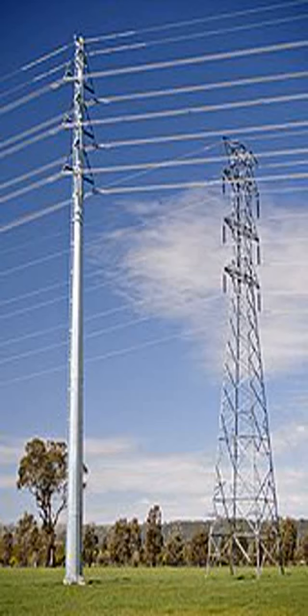Three-phase electric power systems are used for high-voltage transmission lines too. The towers must be designed to carry three conductors. The towers are usually steel lattices or trusses, and the insulators are either glass or porcelain discs or composite insulators using silicone rubber or EPDM rubber material, assembled in strings or long rods whose lengths are dependent on the line voltage and environmental conditions.